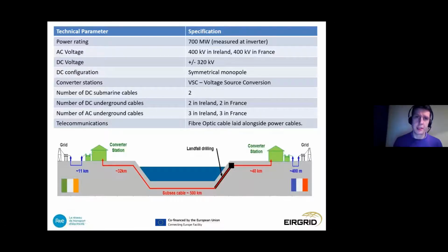In terms of the technical parameters then of the Celtic Interconnector, it will be approximately 575 kilometers in length, and it will link the Knockraha 220 kV substation in East Cork to the La Martyre 400 kV substation in Brittany. 500 kilometers of that will be in the offshore area, and then we will have 35 kilometers of land cable in Ireland and 40 kilometers in France. The interconnector will have a power transmission capacity of 700 megawatts, and this was set based on studies and analysis of the network strengths both in Ireland and in France.